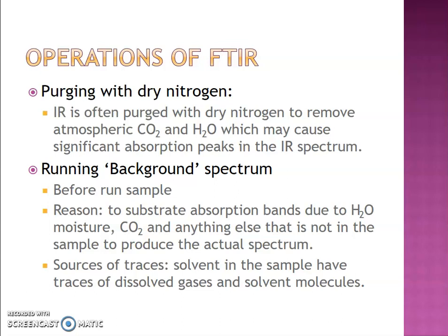And then the second thing that we must do before running the instrument ataupun run the analysis, we must do background scanning. Okay, before run the sample, we need to perform background scanning ataupun running background spectrum. The reason is to subtract absorption bands due to water, moisture and carbon dioxide and anything else that is not in the sample to produce the actual spectrum. Okay? Even though we have already purged with the dry nitrogen, there is still some moisture and carbon dioxide left in the instrument yang kita tak boleh nak use.